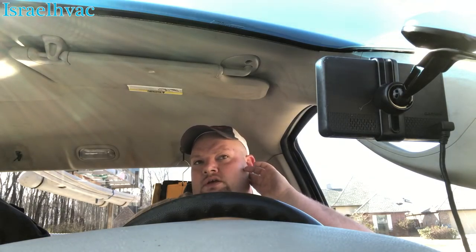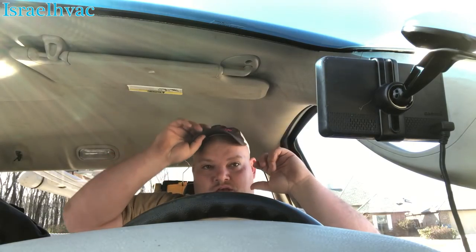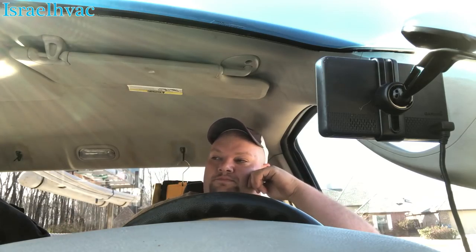I've talked a lot of trash about Lennox over the years, but the Lennox equipment is not horrible. They just need to go aluminum, because the only thing I'm worried about is the warranty nightmare — like I had at that other company — the evaporator leaks were just unbelievable. But I know Lennox is in the process of moving their cased coils, when used with a gas furnace, to aluminum. The air handlers are still some copper, some aluminum — some of the air handlers we're getting with Lennox are aluminum, some are still copper. So the transition is being made.